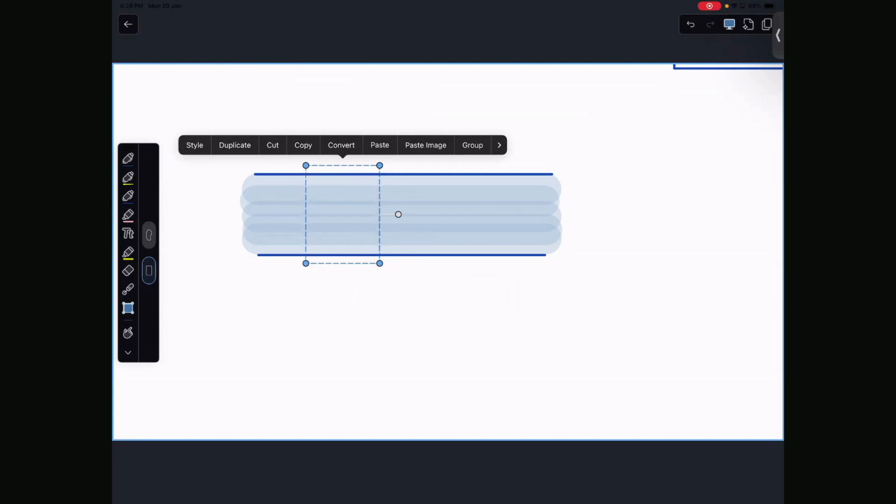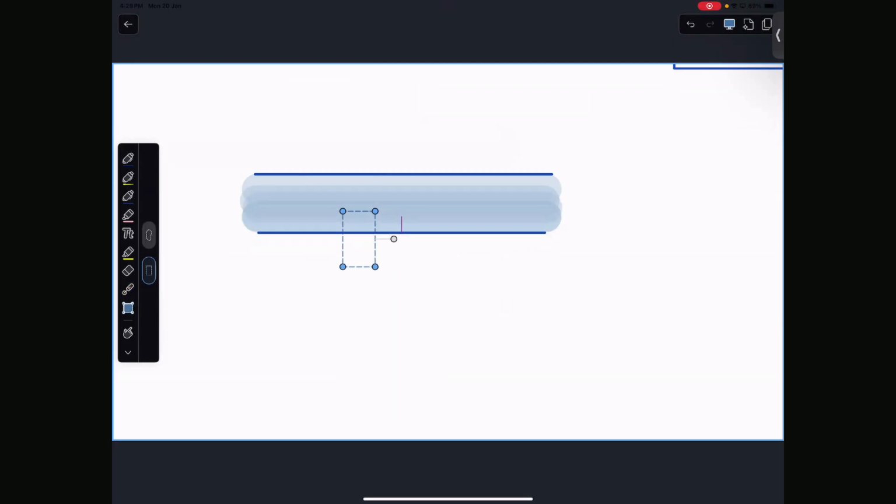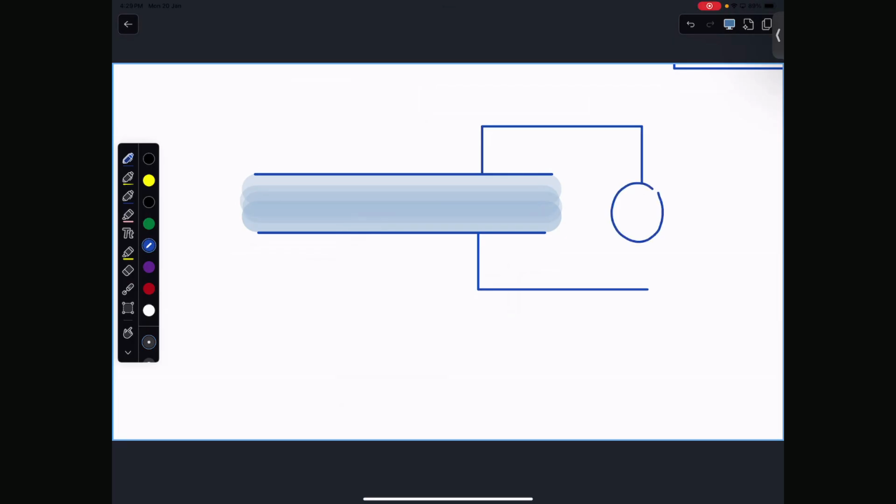So when you have this crystal doing nothing and a wave shows up, isn't a wave a series of compressions and rarefactions? As the wave shows up, it pushes this thing inwards, right? If you have a voltmeter attached across it, what will it read? A voltage. And the voltage is directly proportional to the compression it undergoes. So from the voltage you can figure out not only the wave coming back, but the intensity of the wave coming back. Are you with me so far?